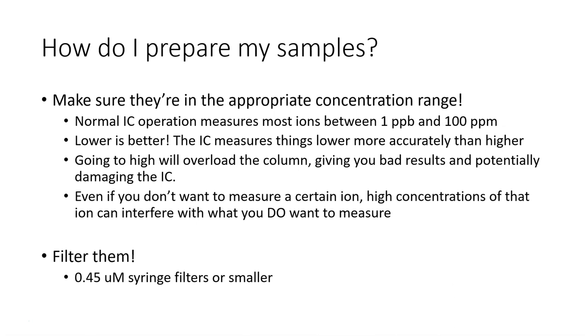The first thing you want to do is make sure that they are in the appropriate concentration range. Normally the IC measures most ions between one part per billion and a hundred parts per million. In general, you want to go lower. Lower is better. The IC measures things lower more accurately than it does higher.